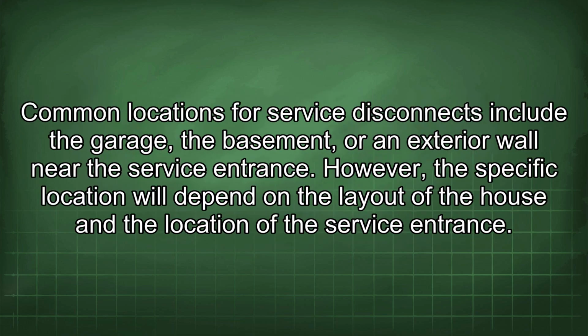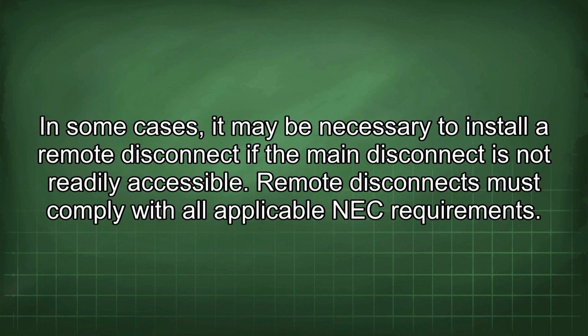Common locations for service disconnects include the garage, the basement, or an exterior wall near the service entrance. However, the specific location will depend on the layout of the house and the location of the service entrance. In some cases, it may be necessary to install a remote disconnect if the main disconnect is not readily accessible. Remote disconnects must comply with all applicable NEC requirements.